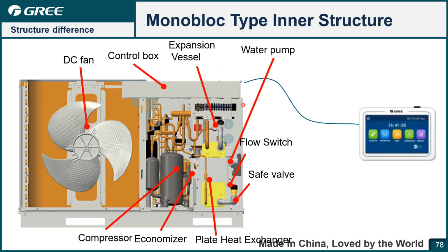For the monoblock type, you can see the first difference is no 3-way valve. Yeah, no 3-way valve. You have to install it by yourself. And also the expansion vessel is a cylinder. Yeah, and also the controller is external, not built in. You need a cable to connect with the PCB.